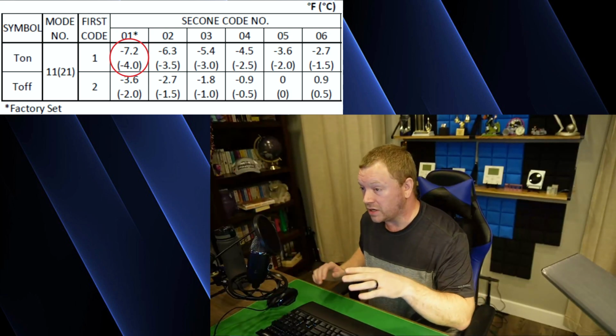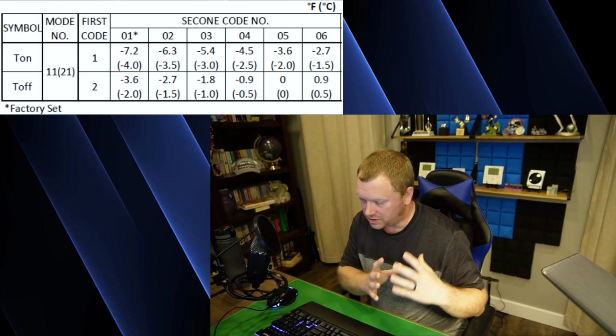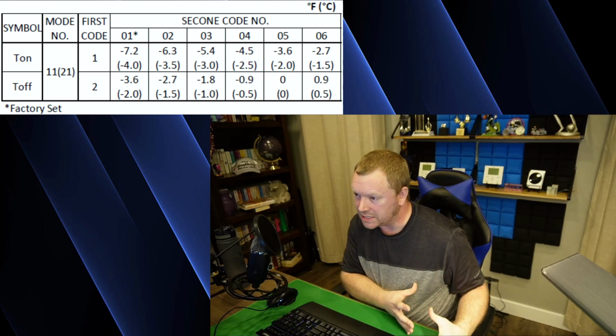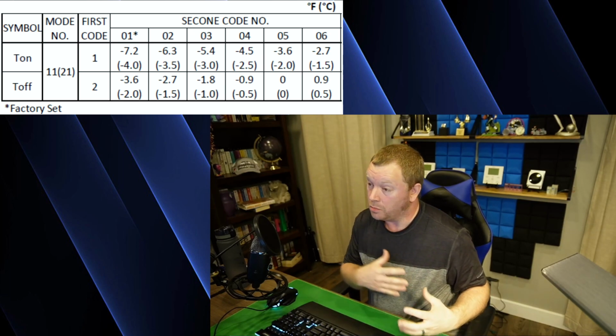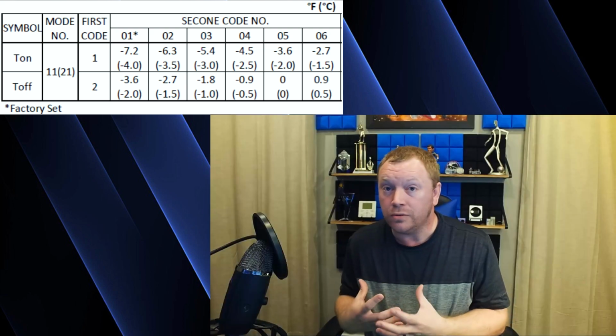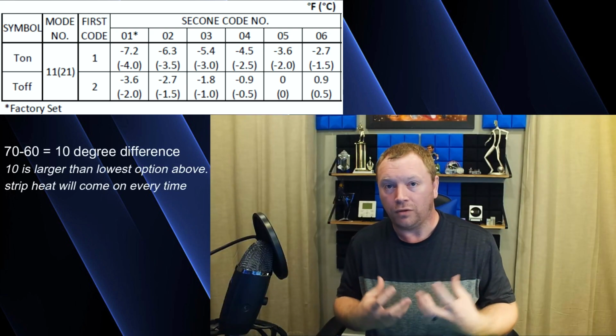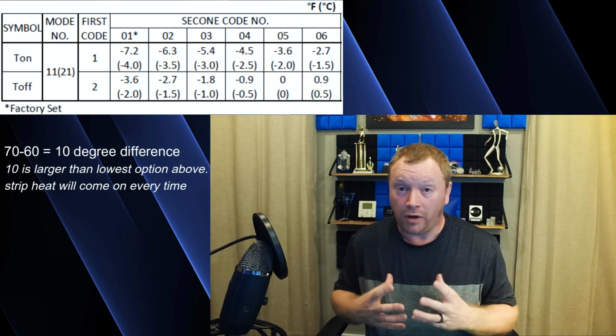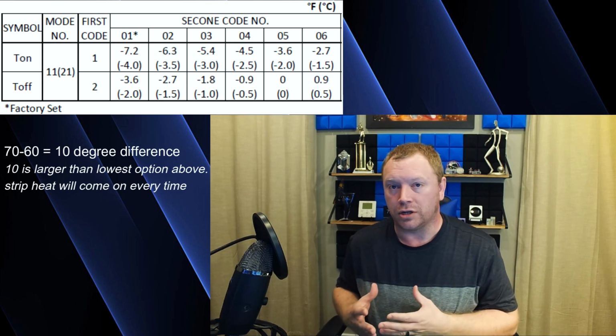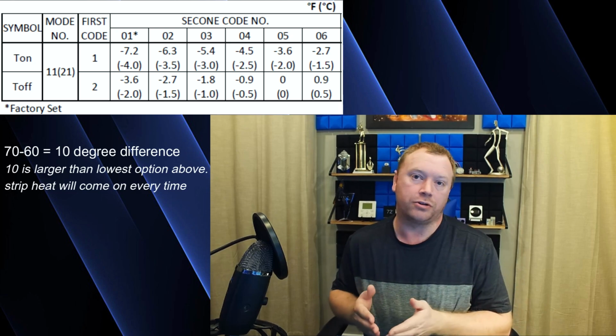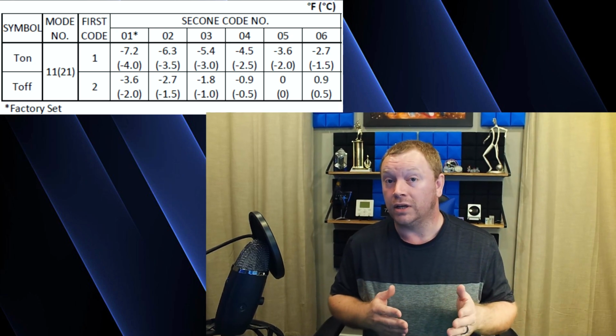So if you have a customer, an end user, a homeowner who sleeps and they set it all the way back to 60, where they turn it off, and then in the morning they want to wake up to 70 cozy temperatures, right? Warm floors to put their feet on or whatever, fine. But your strip heat's going to come on every single morning. That strip heater is going to turn on, and guess what? That bill is going to go through the roof. That's going to be the customer that calls and says, hey, why is my energy bill triple what it used to be before I got this VRF system? Come back, pull this thing out. This thing is costing me an arm and a leg.